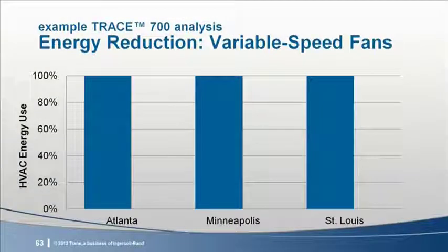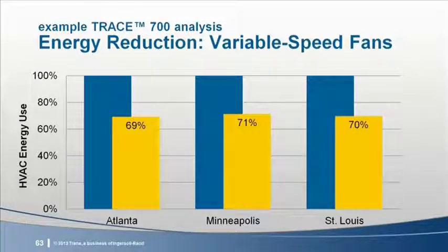The next alternative, variable speed fans, uses VFDs to control the fan motor speed. By simulating the same buildings with variable speed fans, system energy consumption is reduced even further, by several percent for each location. This analysis assumes variable speed airflow for both cooling and heating. The space types simulated rarely operate at design airflow, which allows for significant run hours at part load.